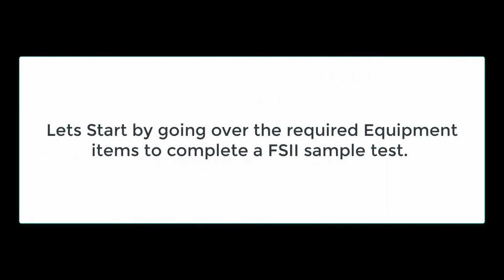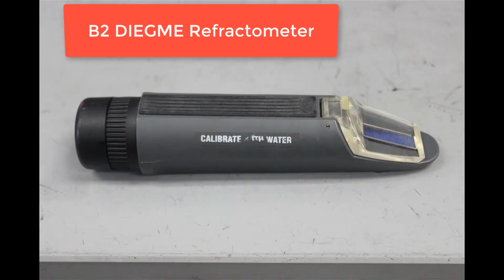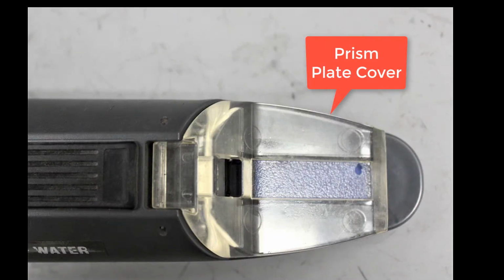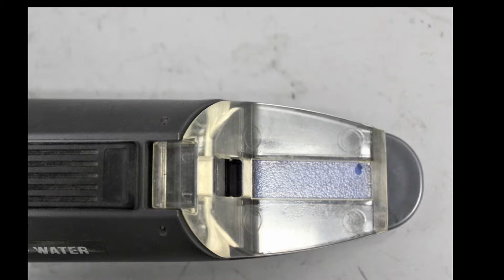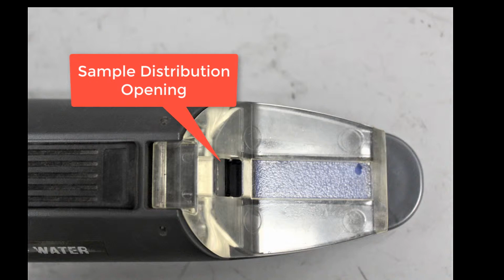Let's start by going over the required equipment items to complete a FSII sample test. Here you'll see a B2 refractometer. The refractometer measures diethylene glycol monomethyl ether in percent by volume, also known as DiEGME. It's a delicate piece of equipment. Here you see the prism plate cover used to protect the prism from outside sources and scratches. You also have a small opening to be able to distribute the sample through.